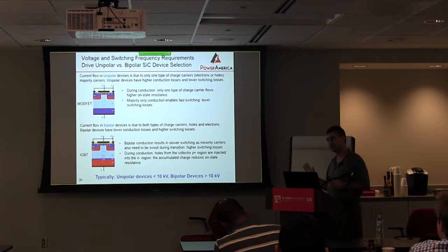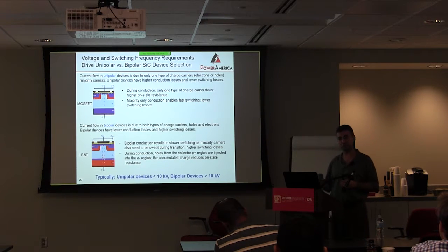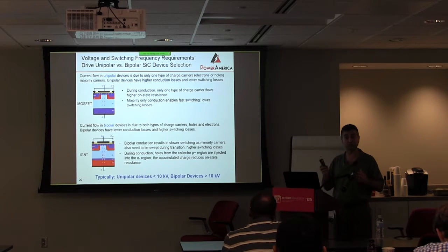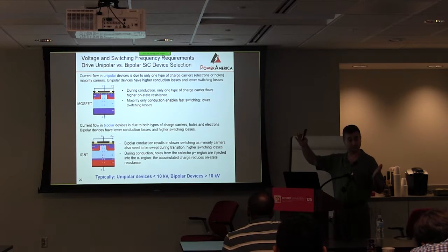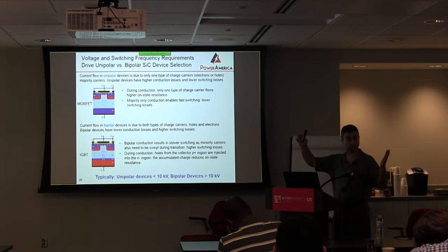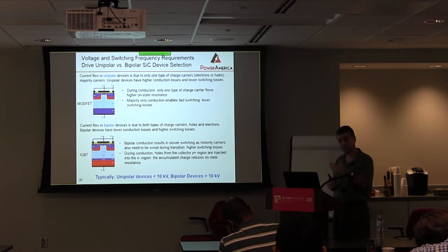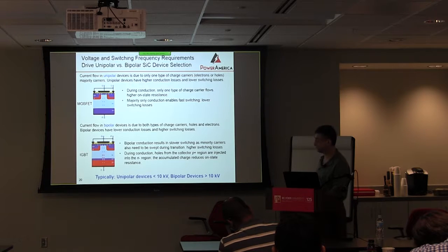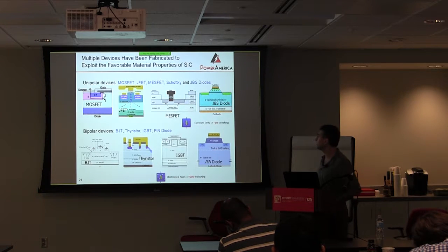In silicon carbide, generally speaking, up to 10 kV, people typically use unipolar devices like a MOSFET. Once you exceed 10 kV, because conduction losses become substantial due to the thick layer needed to get to 10, 15, or 20 kV, you go into bipolar type devices.